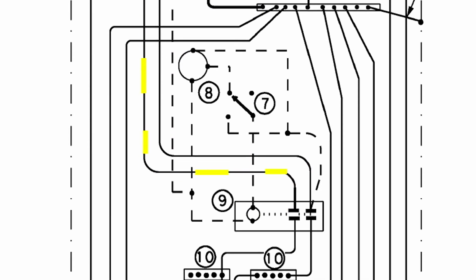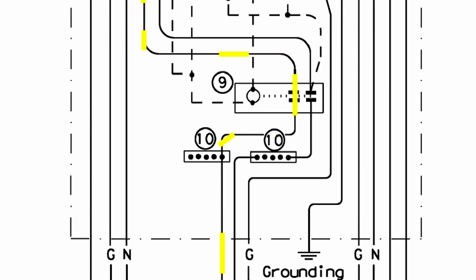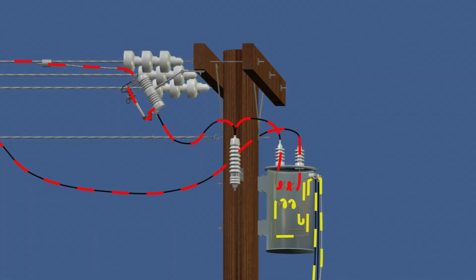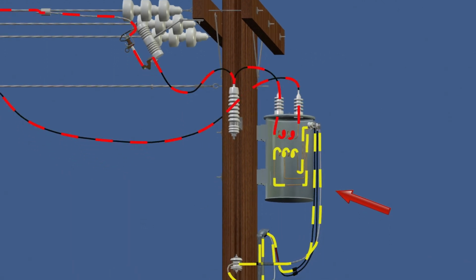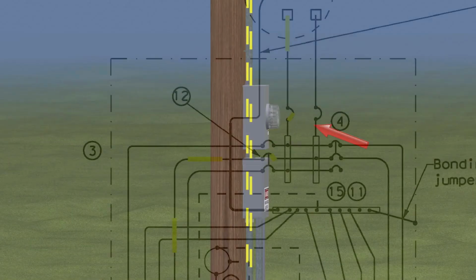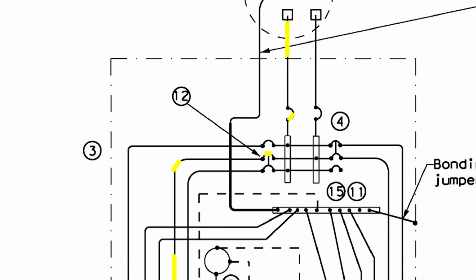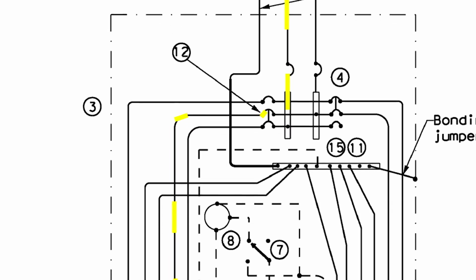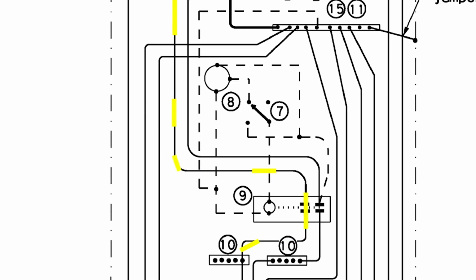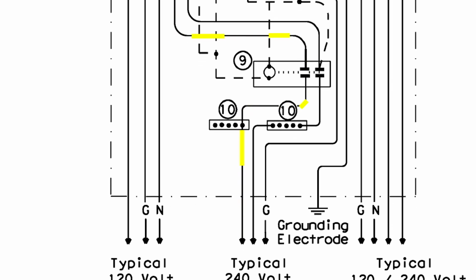From the load side of the lighting contactor, 2 conductors connect to 2 insulated blocks mounted in the enclosure, called power distribution blocks. The light circuit conductors from the field run back to the 2 power distribution blocks, completing the circuit. Electrical power flows from the utility transformer through the service drop and down through the service entrance conductors. The power moves through the meter, through the main breaker, to the bus bars of the load center. From the bus bars, the power then moves through the branch circuit breakers, through the lighting contactor, through the power distribution blocks, and out to the light fixtures.